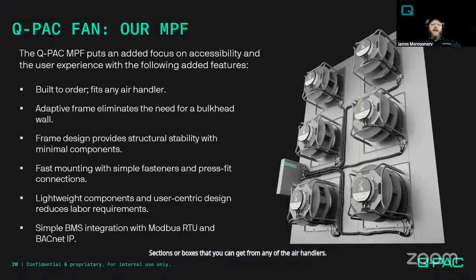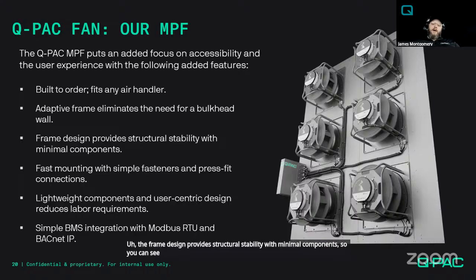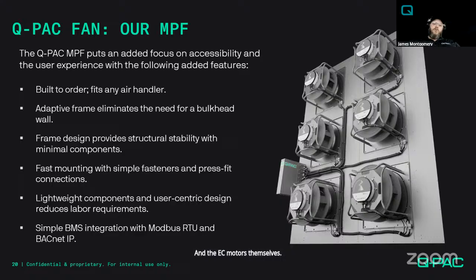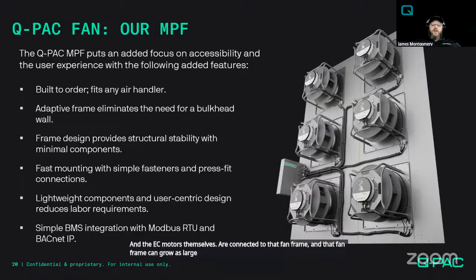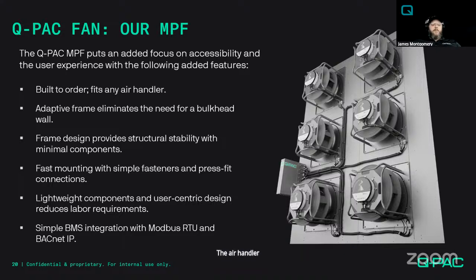Our adaptive fan frame eliminates the need for a bulkhead. I'll go into that in just a second. The frame design provides structural stability with minimal components. So you can see there, we've got a multi-motor plenum fan, and the EC motors themselves are connected to that fan frame. And that fan frame can grow as large or as small as you need it, depending upon the air handler size internal requirements.